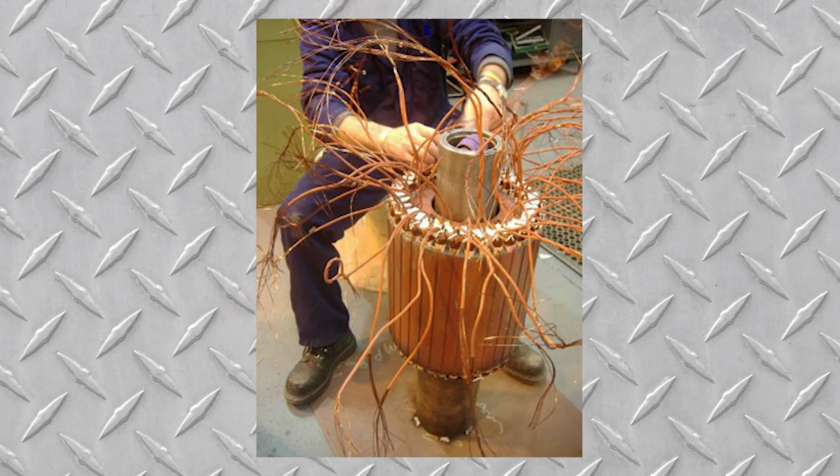Now, you have these windings on the motors that create the magnetic fields. These magnetic fields cause the motors to rotate, and when these windings burn out and you want to rewind it, the question is, can you do that in a way that doesn't hurt the efficiency of the motor? The answer is yes. If you take your time and you rewind it by hand, you can come back with a motor with a higher efficiency than the original motor.